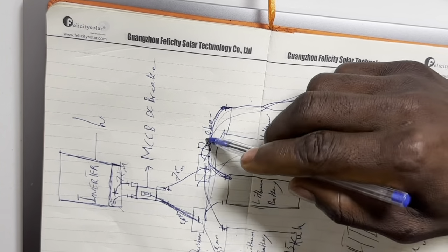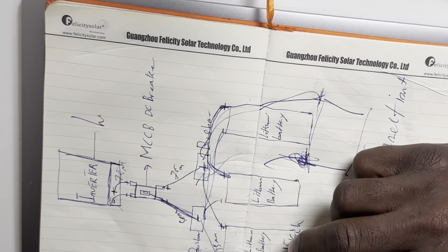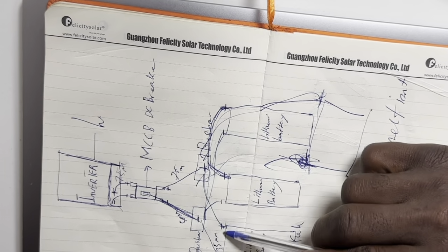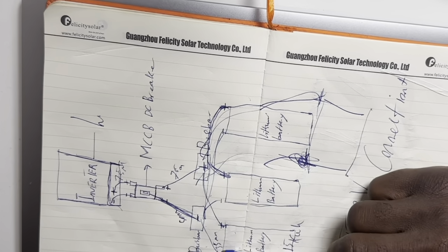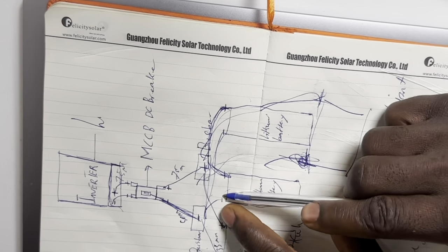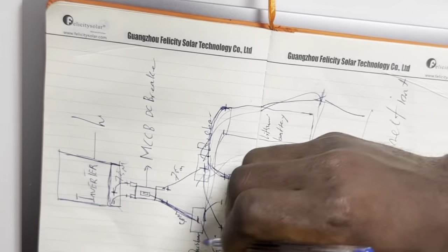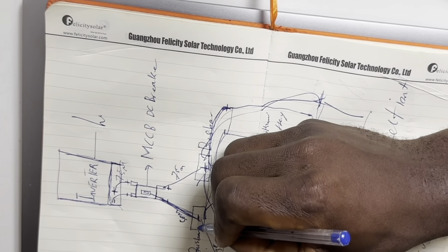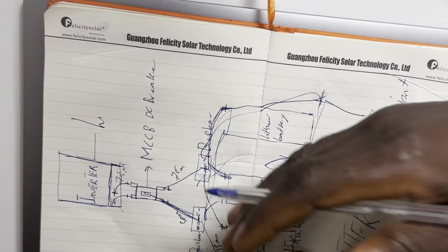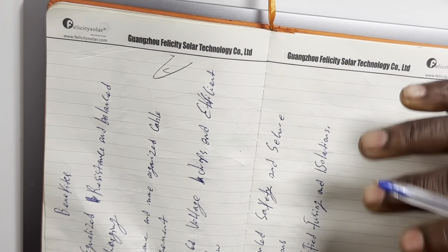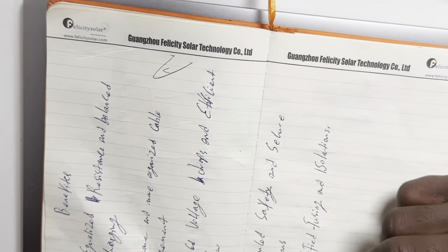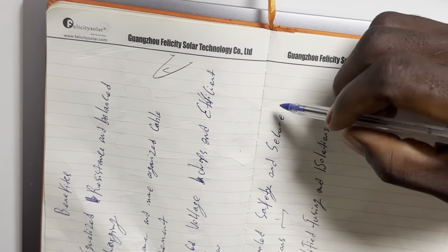But once you have your bus bar, tightening the battery terminals becomes very easy, because you only have one cable coming in and one going to the terminal. Inside the terminal there are micro points, tiny contact points for each battery you want to connect. This ensures more safety for the installation and secures the connection port as well.